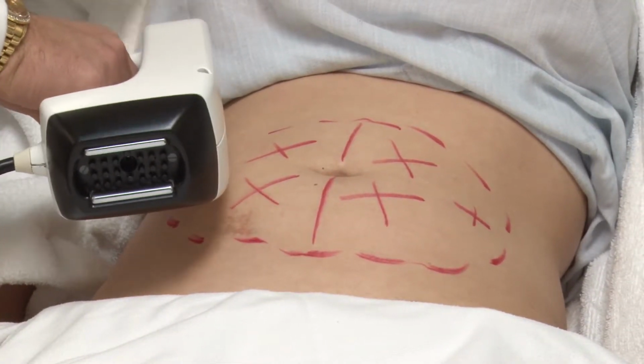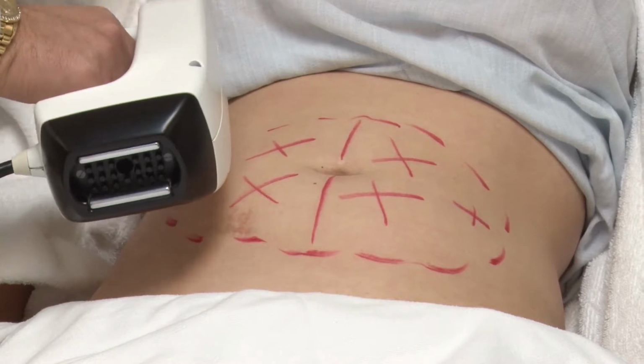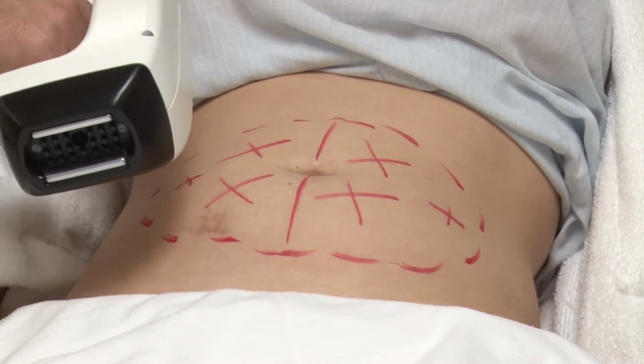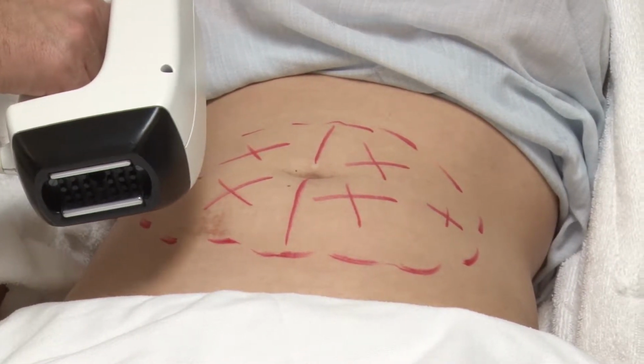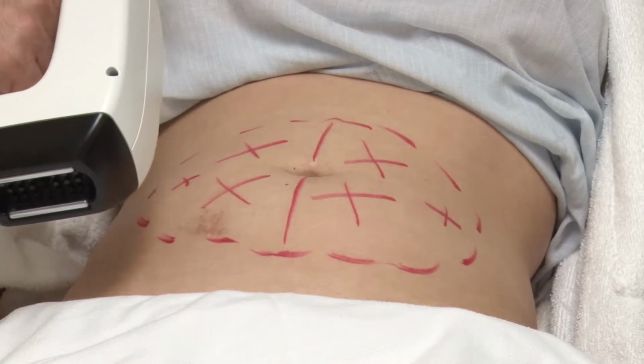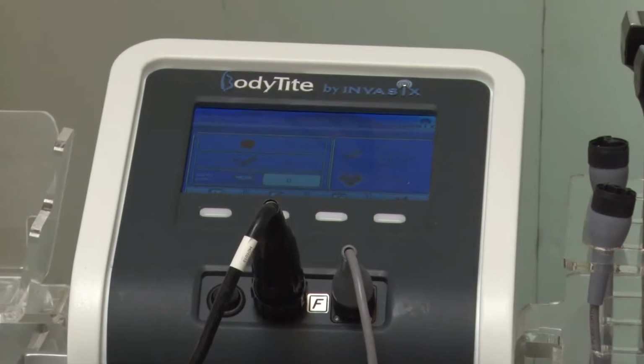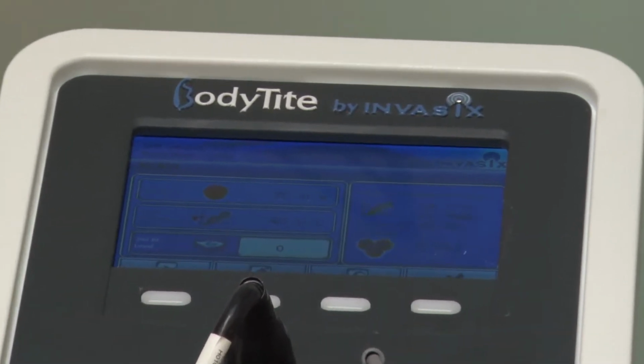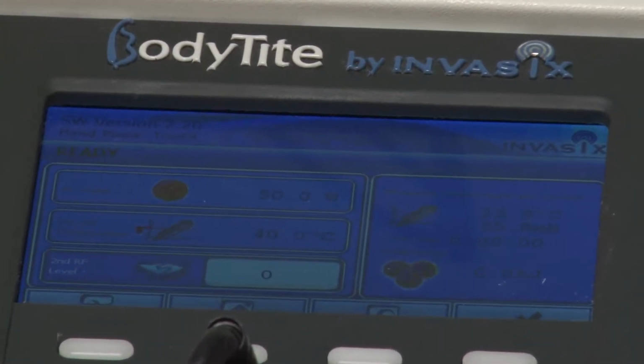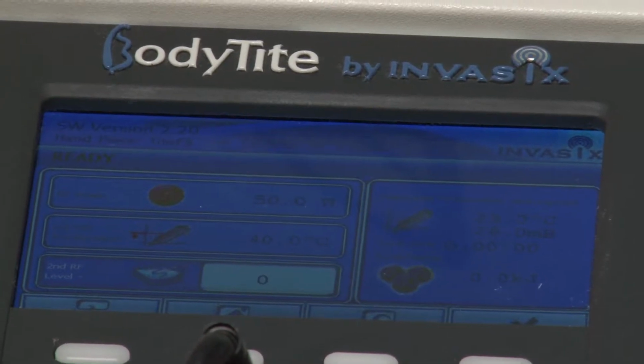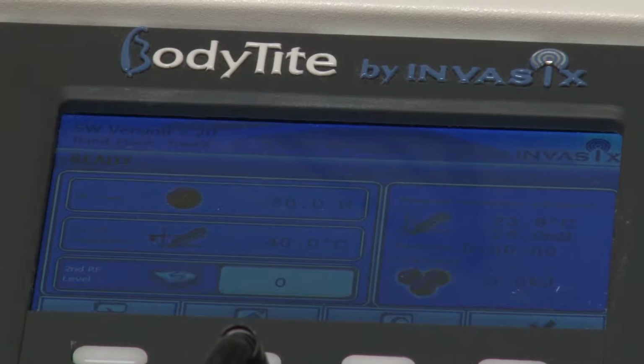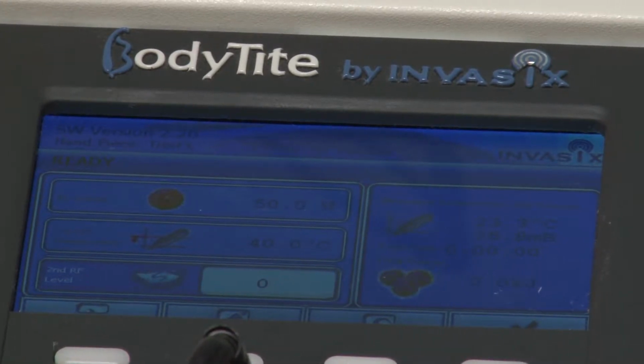Okay? Now, again, we're going to take this suction-coupled applicator and we're going to walk the patient the very first time through what suction feels like. So I'll do a few pulses so they get used to 350 millibars of suction. So we're going to hit the ready button. We're set at 50 watts. You can go back to the system. Just show the system there if we can zoom in. Again, we've set this, if you zoom right in, at 50 watts of energy. 40 degrees Celsius, that's not our endpoint. I want them to get used to suction and heat first, and 0 for second RF. We'll gradually go up during the first few minutes to get them used to this.